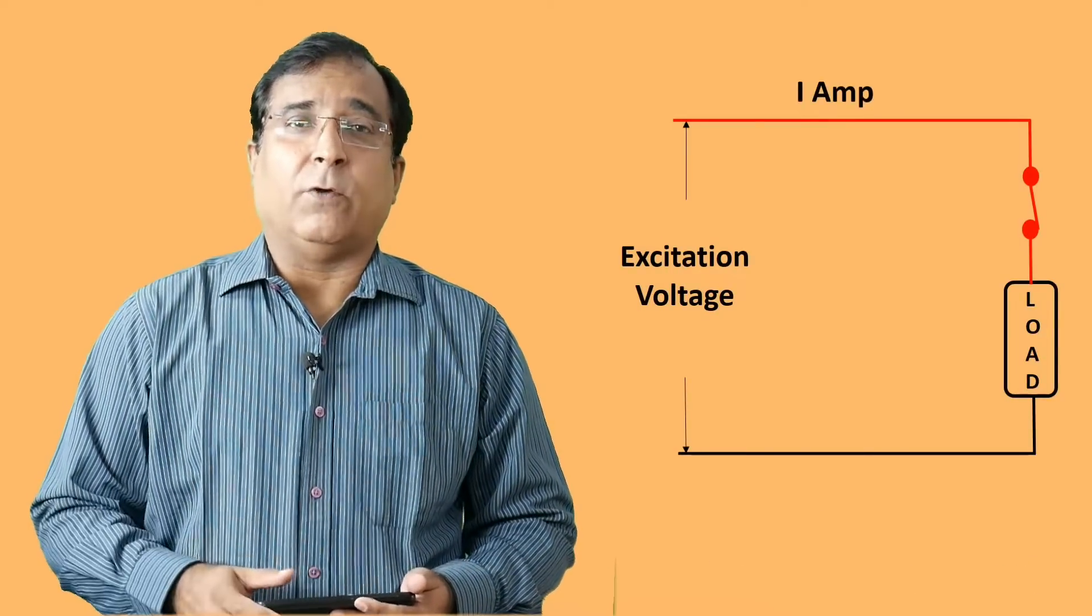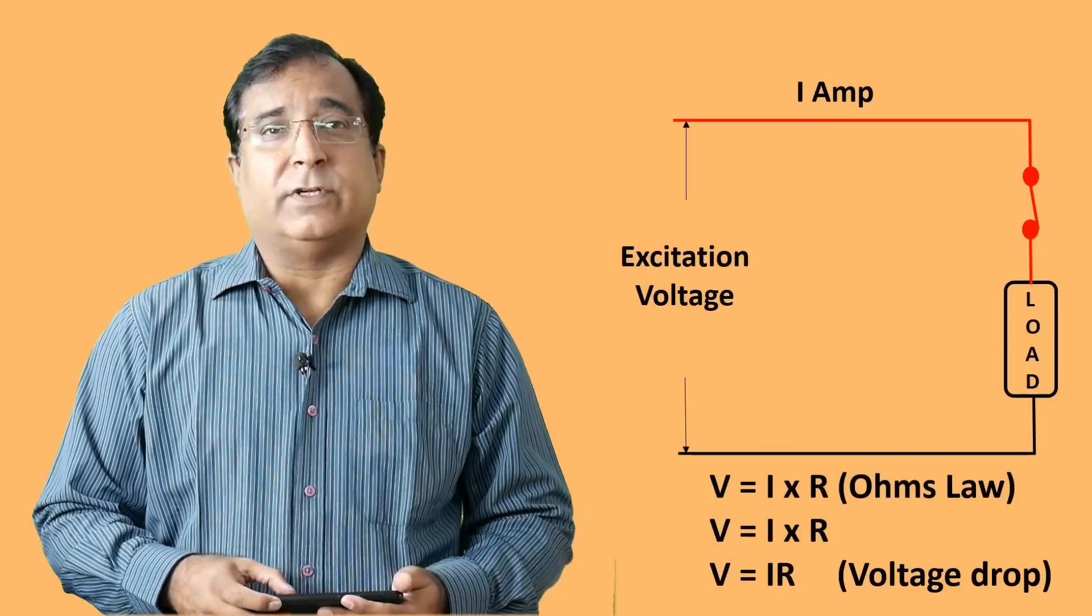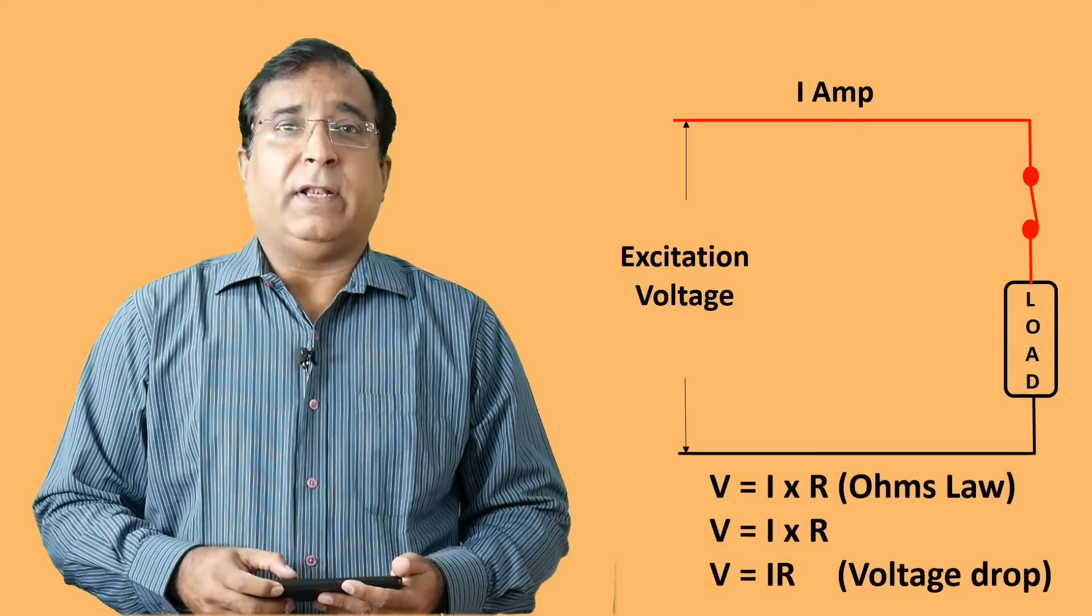As the current starts flowing, Ohm's law is applied here and it causes voltage drop. If the cable length from the load cell to the indicator is very short, then this voltage drop is not reflected in the measurement and can be compensated as fixed. That's why only 4 wire load cells are used in local machine.